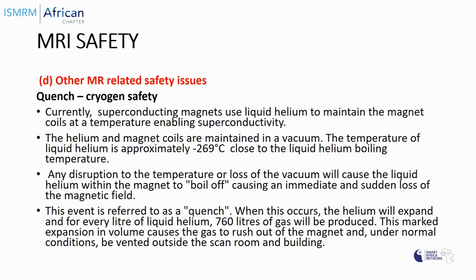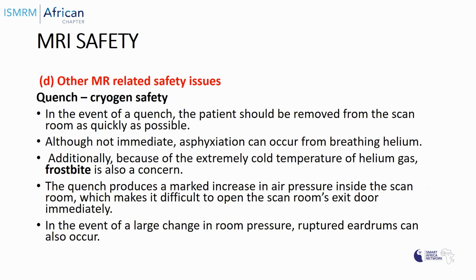So any disruption to the temperature or loss of the vacuum will cause the liquid helium within the magnet to boil off, causing an immediate and sudden loss of the magnetic field. This event is referred to as quench. When this occurs, the helium will expand, and for every liter of liquid helium, 760 liters of gas will be produced. This marked expansion in volume causes the gas to rush out of the magnet and, under normal conditions, be vented outside the scan room and building.